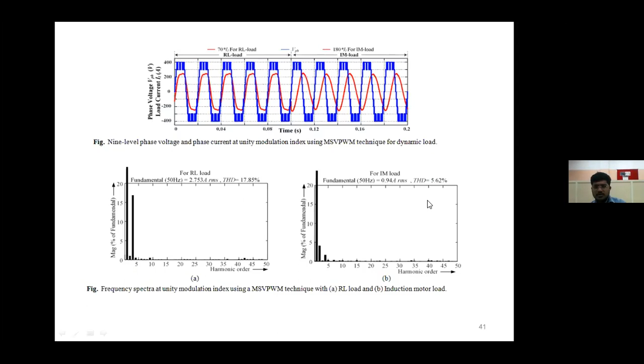If you see, this is the phase current or load current with THD 17.85, which happens due to this dominant third harmonic. This happens because the load neutral and inverter neutral are connected. If they are not connected, then these third harmonics may not be present. That is my observation. And this is the induction motor load, where you can see 5.62 THD, and these are the experimental results.